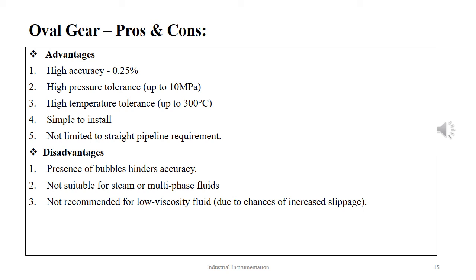The limitations are, however, presence of bubbles hinder accuracy, not suitable for steam or multiphase fluids, and not recommended for low viscosity fluids.